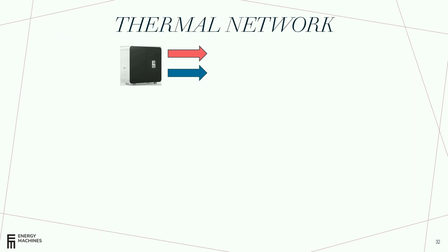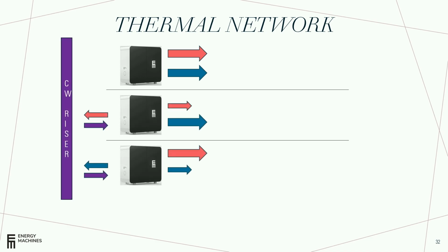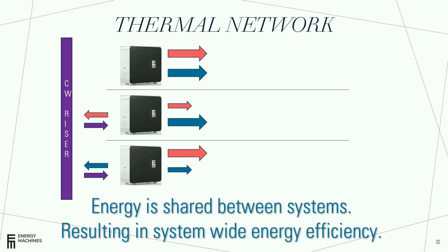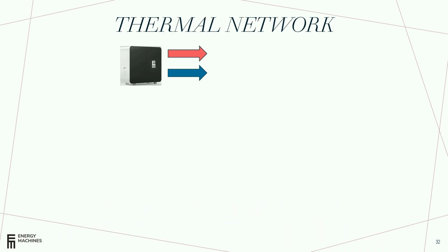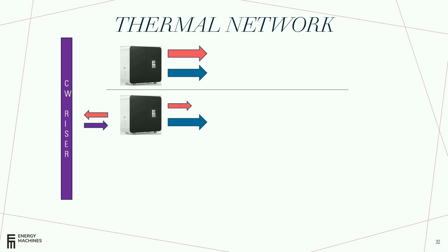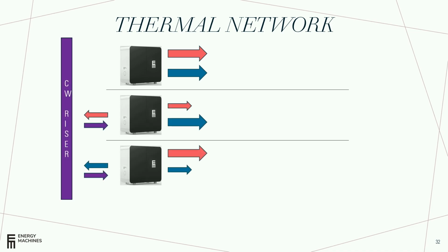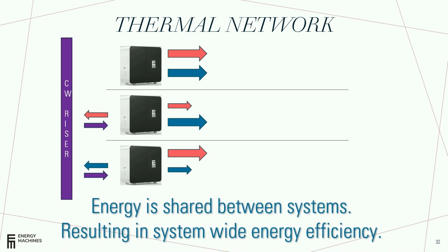So with the thermal network, this is how energy recovery is done on the chilled water side most days. The energy recovery on the top side is basically when the heating and the cooling loads magically balance, right? And this is your unicorn scenario. If the chilled water side drops in capacity, by nature your hot side has to drop, unless you can have some self-balancing mechanism that corrects for that. And so really, these next two scenarios are where you typically live 99.9% of the year.